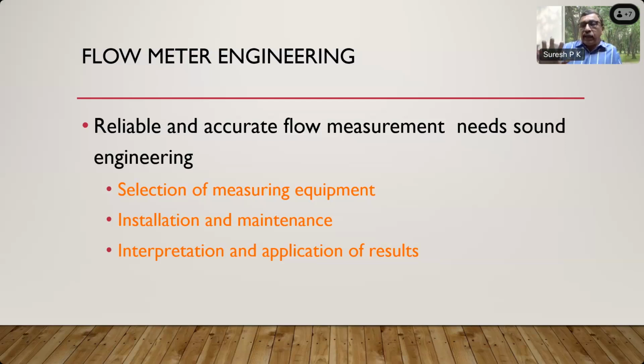I have seen certain applications where you have designed and applied a mass flow meter for a particular place, and then you have increased the flow. Increasing the flow means increased pressure loss, and increased pressure loss means a probability of two-phase flow inside the flow meter, and cavitation. Cavitation can result in inaccuracy of the flow. So basically two phases inside the flow meter will result in cavitation, and probably damage to the flow meter in the long run. All these things can happen.